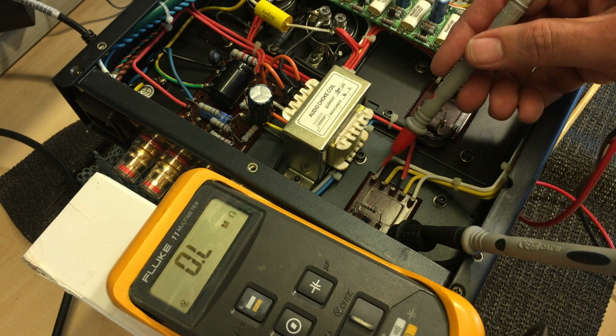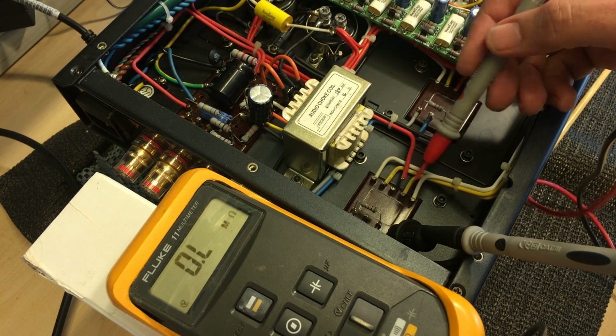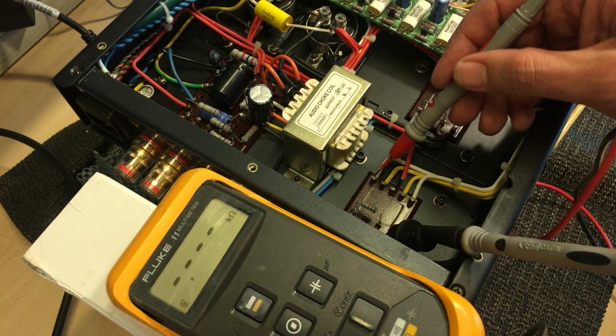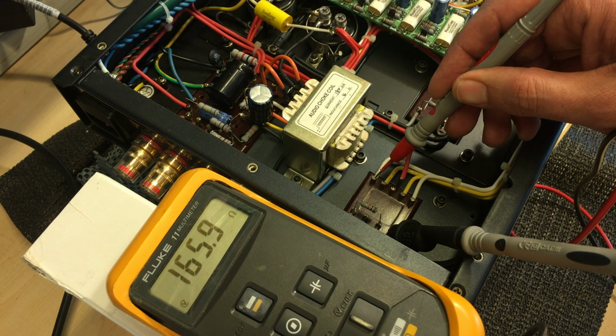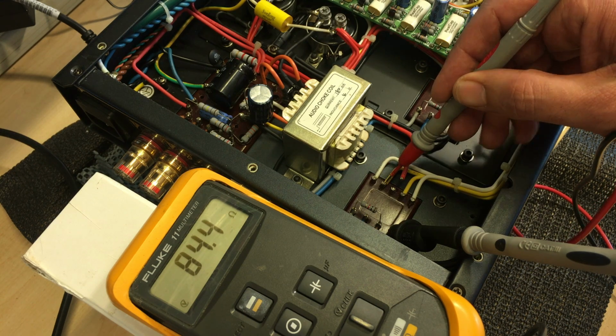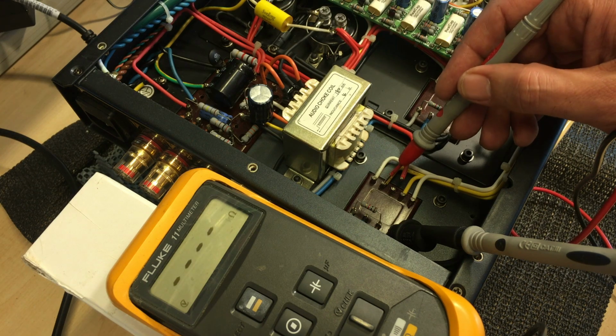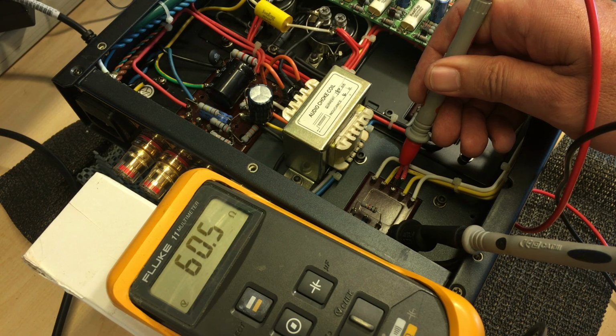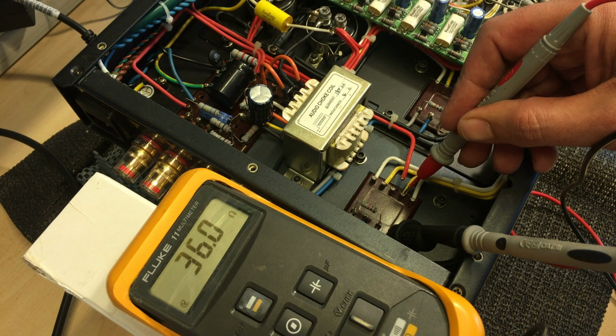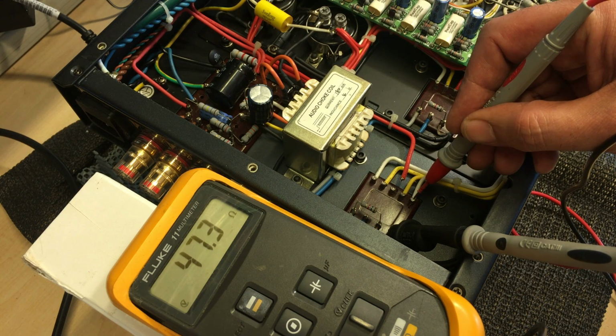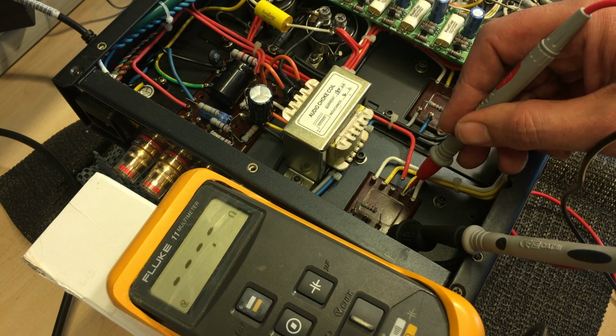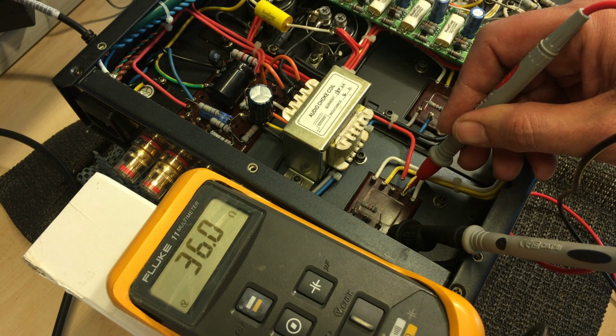To determine which of these is actually creating the short, if there is one in particular, I'm going to measure the resistance on all of them, remembering there's some resistance between these coils. That one is 165 ohms, that one is 85 ohms, so this one is closer to our short since it's lower resistance. That one is 60 ohms, closer still. That one is 36 ohms, that one 47 ohms. So this point has a 36 ohm path to ground.